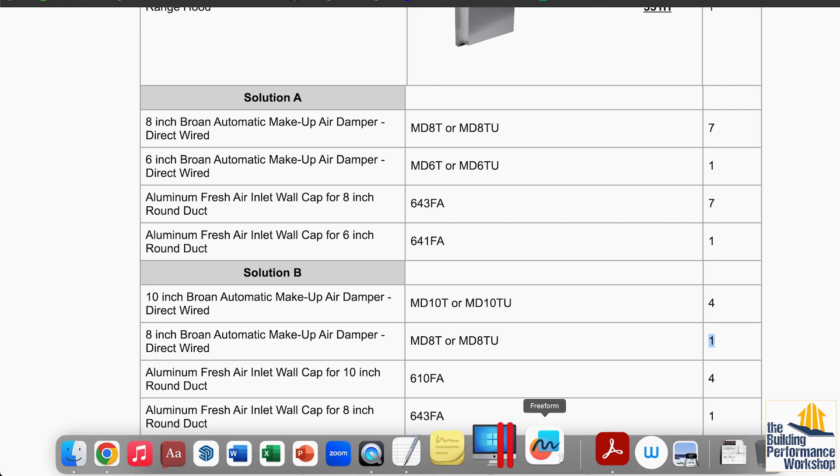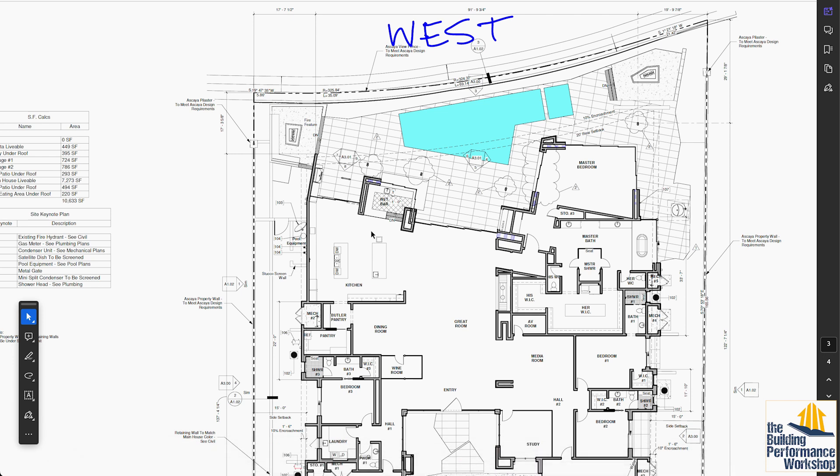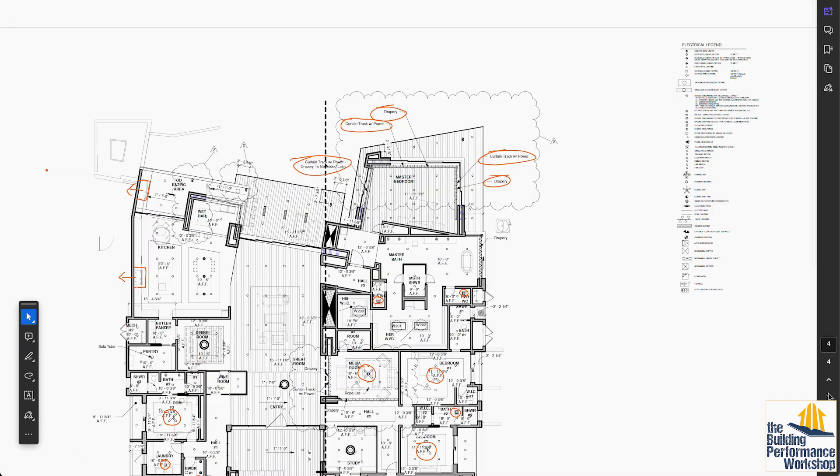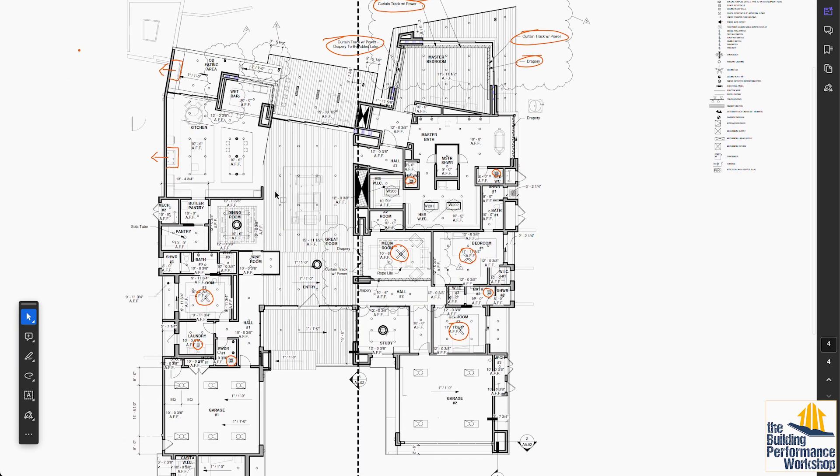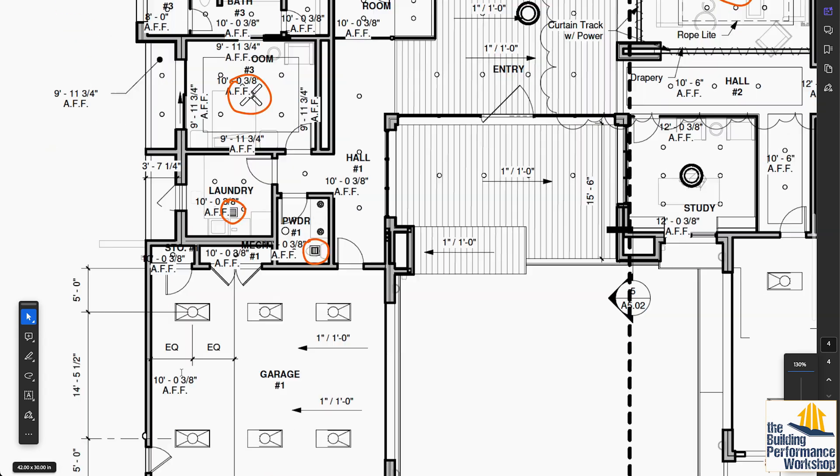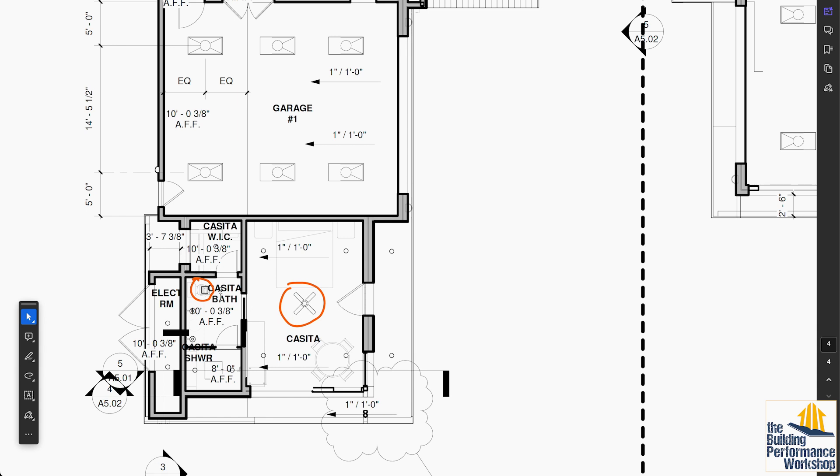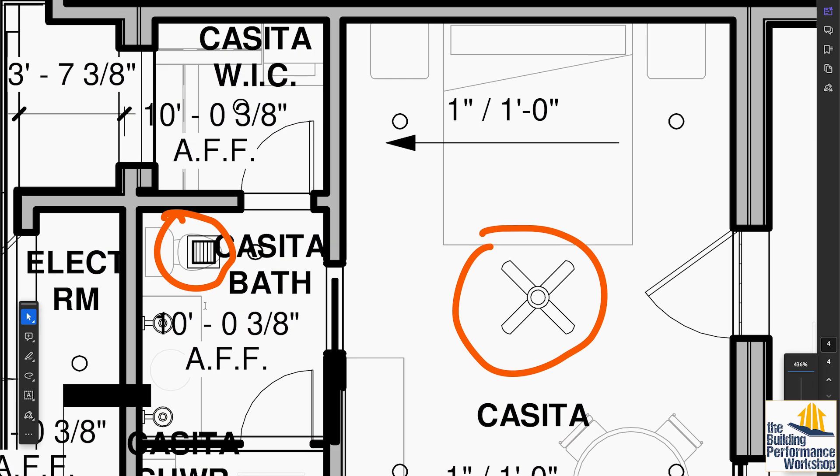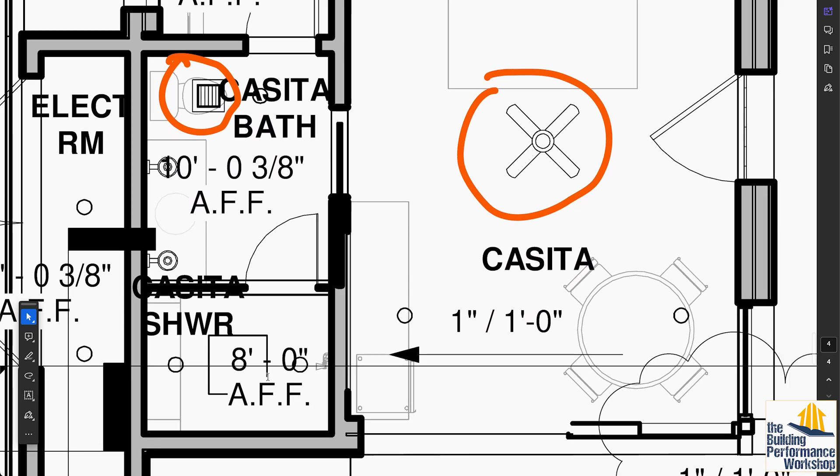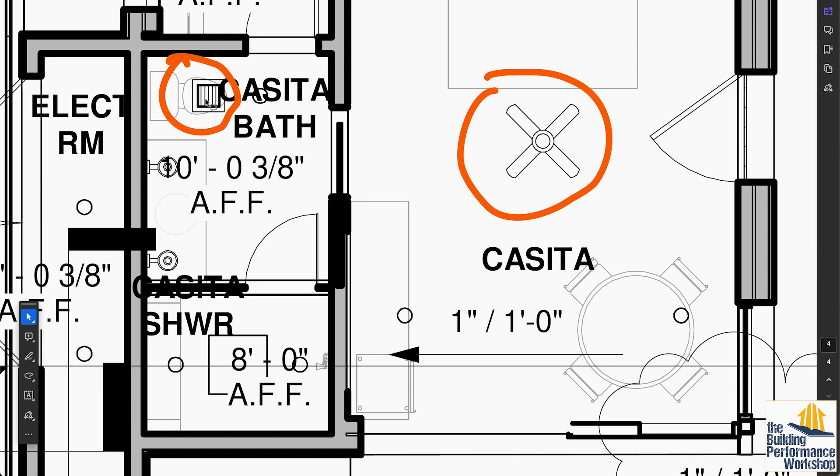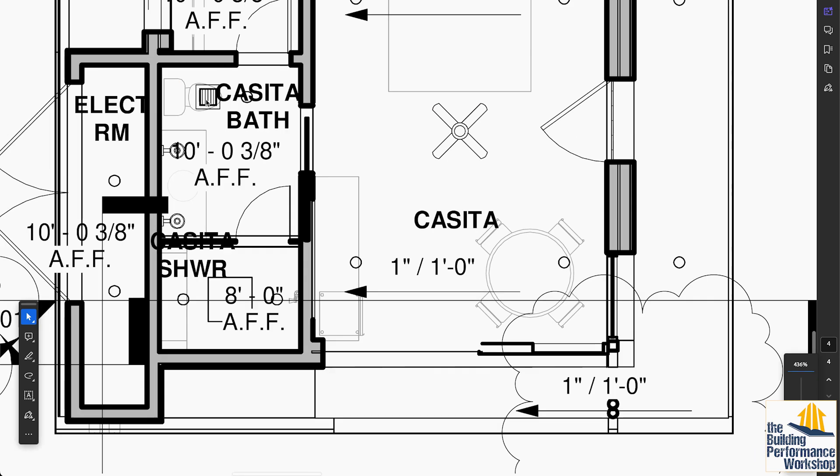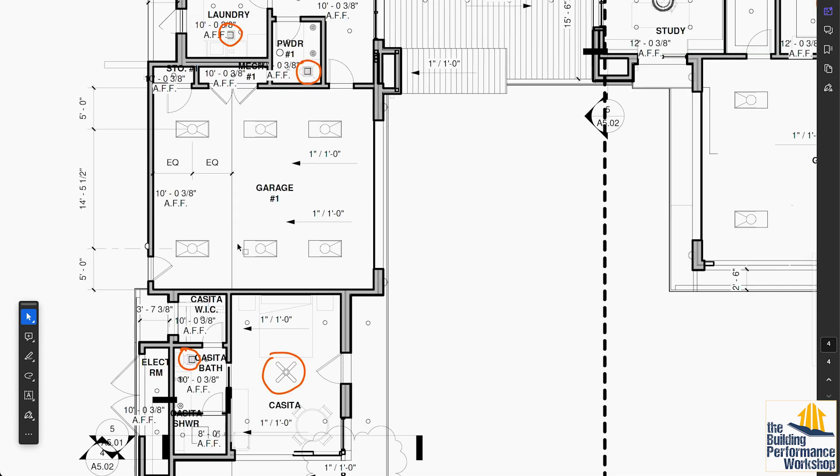Let's look at some of the implications here. Let's go through the plan. We've got right here the mechanical systems. I've just circled some basic stuff. First of all, I love ceiling fans. Great job, because in a higher performance home, even though this one is single story, it's got what looks like code insulation in the roof cavity. Ceiling fans are good because you're going to lower the load. HVAC system is going to be smaller. We have a bath exhaust fan and it's over the toilet in this bathroom. There's a shower right down here that it should actually be in. In fact, if you would put this thing in the shower, the air comes in under the door and goes across the bathroom and hopefully would grab the odors around the toilet on its way out over the shower. So that could be a 2-for-1. When builders call this a fart fan, they end up thinking that that is what it's for. That's not very healthy.